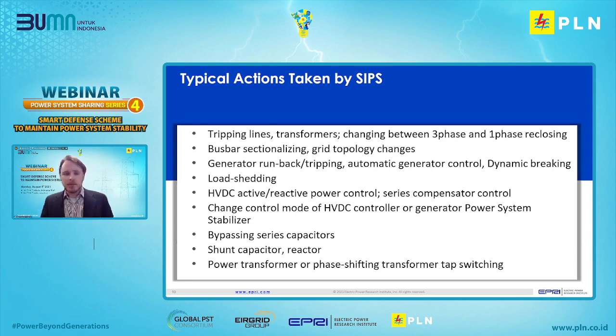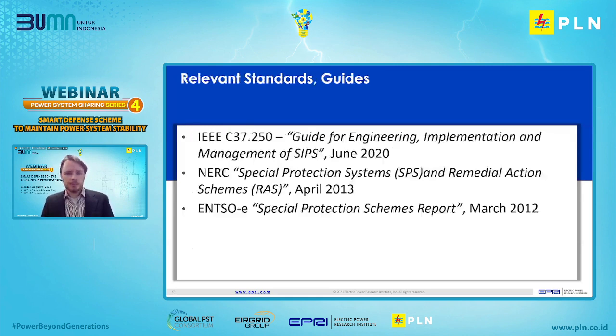And again, covered by the previous speaker, there are many actions that can be taken, typically tripping transmission lines, triggering generators to run back, controlled load shedding, bypassing series capacitors, and things of that nature. Generally, and most commonly, it is tripping transmission lines or triggering generators to run back or trip. These are just some relevant standards. You can move on 2 slides now.